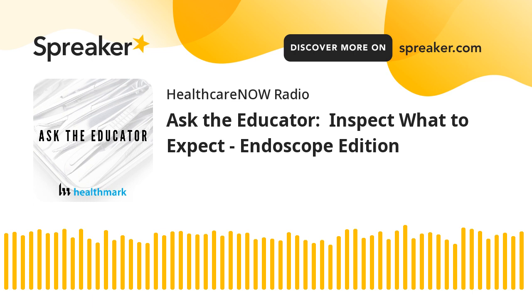Absolutely. I think what you uncovered is some pretty significant evidence that internal damage to our endoscopes does, in fact, impact the cleaning efficacy. And if you're not testing or if you're not visually inspecting, then there are chances that you're missing some contaminated endoscopes in your process, which unfortunately would lead to an increased level of risk. So I think you uncovered some valuable information there. You found a scope that was getting more failures in your cleaning verification test than any other scope, which turned out to be a damaged endoscope. I mean, that's a pretty significant finding. And what else did you discover?